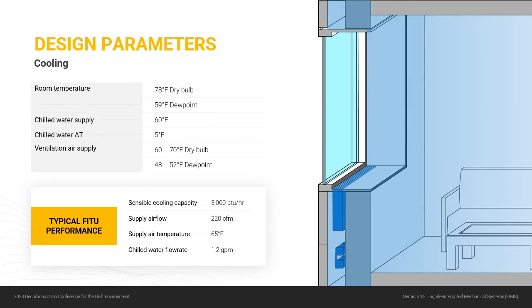When we look at cooling, again, we have to look at dew points and humidity. So we typically want to control to a roughly 59-degree dew point. Chilled water supply has to be just above that, so 60 degrees. Ventilation air, we want to supply roughly neutral. You don't want to go below 60 degrees again because you might start getting condensation on the surface of the duct. And again, with conventional heat pump equipment, 48 to 52 degrees is a pretty reasonable dew point to use.